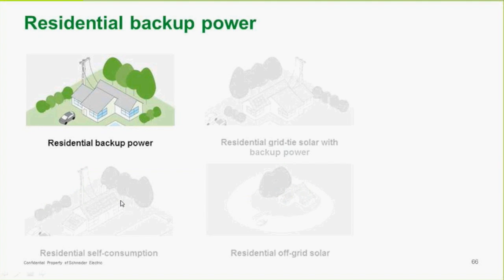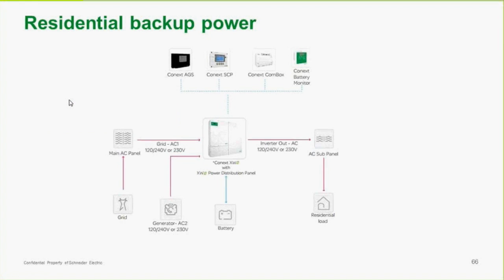So let's look at a few different solutions. Residential backup power. So here's what a diagram might look like. You have the grid coming into the main AC panel, and we're providing power to the inverter, as well as you would be providing power to a lot of the other heavy loads in the house that are beyond the capability of the inverter. The inverter is tied to a sub-panel, and the sub-panel is where your critical loads are. And we have, in this case, a generator that's ready to go, and we have a battery in the system. And normally we wouldn't have all of these things.